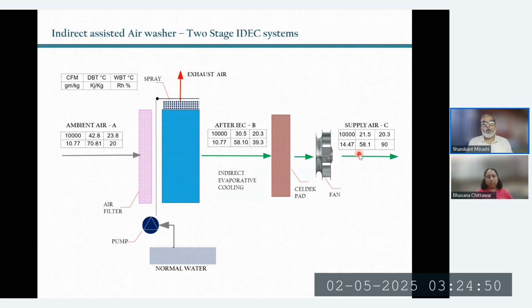Now, is this lower temperature alone going to be beneficial? Yes and no, both, because I will have better comfort inside the space. Anybody can agree to it. If you look at it from a design perspective, any HVAC consultant here in the audience will agree, when I'm designing a system, if I have to cool a factory premise and somebody says I've got X amount of heat load, we as consultants understand what heat is sitting inside that place, heat by virtue of the building gain, by virtue of people, by virtue of whatever heat process inside. So we understand how much cooling we have to arrive at. So if I have an X square meter factory premise, we sit down and do the heat load calculation and say, okay, there's a 1 lakh square feet factory shed. It has got 100 ton equivalent heat to be removed.